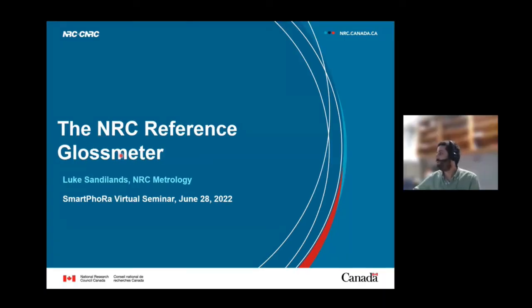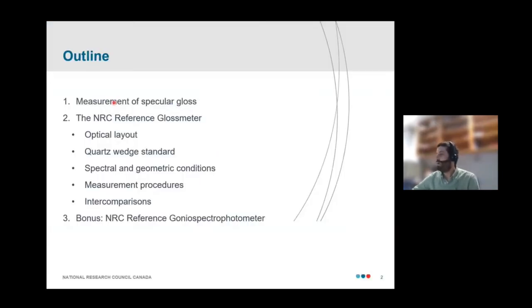My presentation will be a description of our reference gloss meter, which is an instrument that's been in use at NRC since 1970. And this is what we use to carry out calibrations of specular gloss. Can I just confirm that everyone can see my slides okay before I go on? Great.